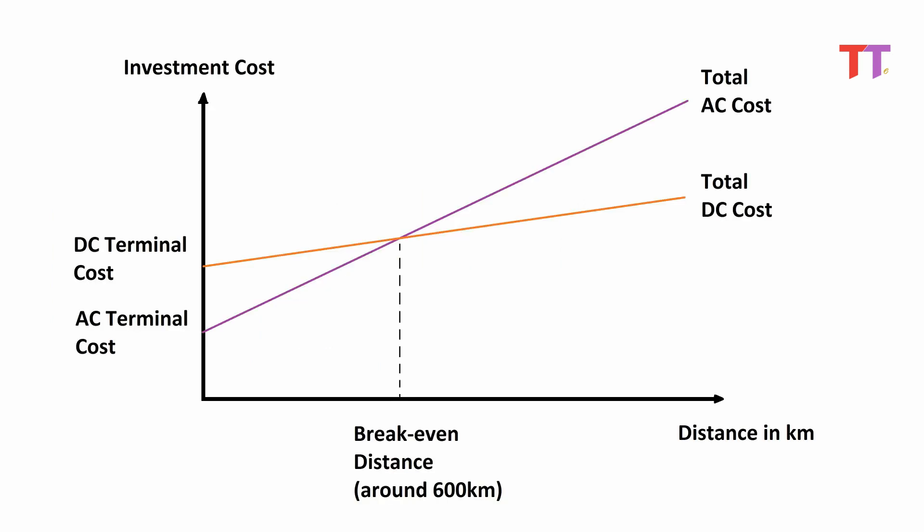Considering the capital cost and for better understanding of the economics of both systems, let's see the graph. HVAC transmission cost and HVDC transmission cost are plotted against distance of transmission lines in kilometers. As shown in the graph, up to the break-even point at around 600 kilometers, cost of HVDC transmission is higher than that of HVAC. Whereas after 600 kilometers, cost of HVAC transmission is higher than that of HVDC. Hence for transmission beyond 600 kilometers, HVDC transmission system is more economical.